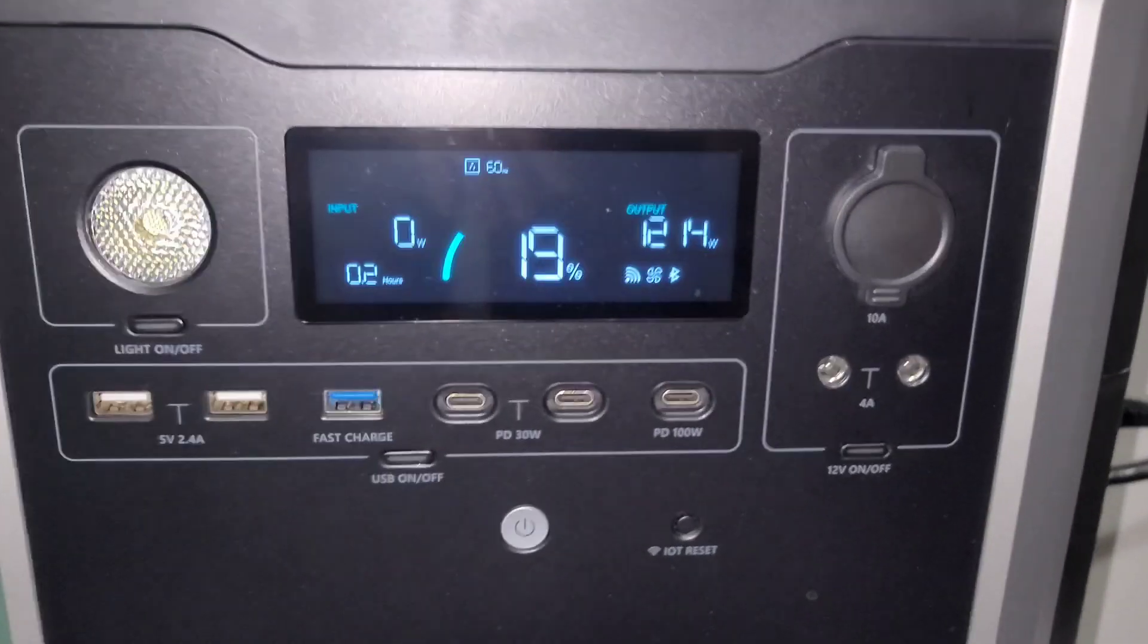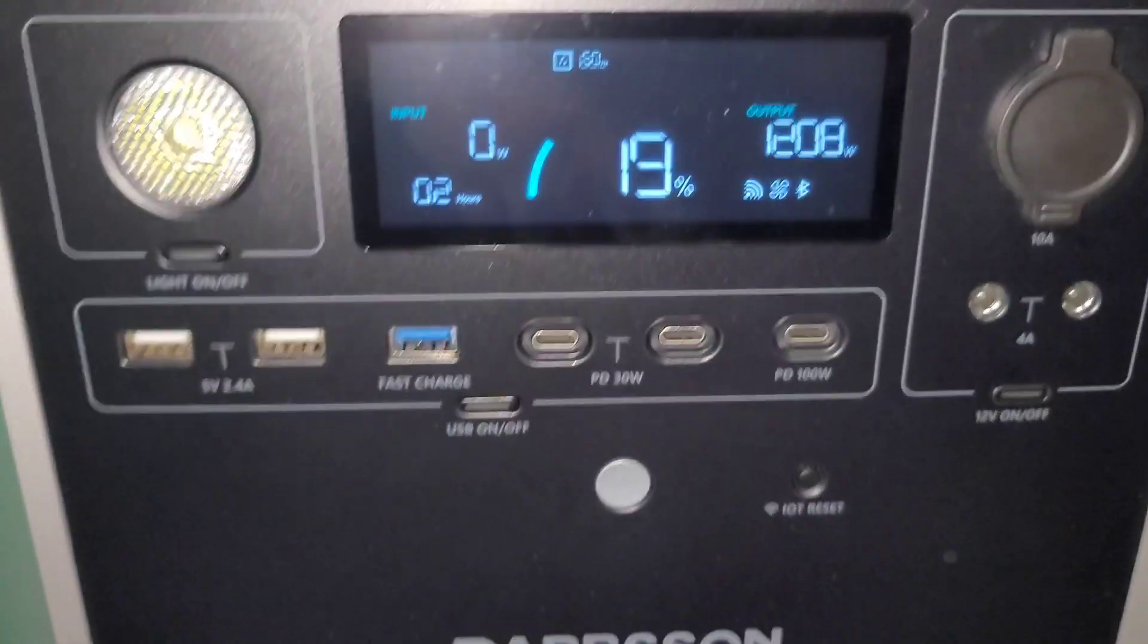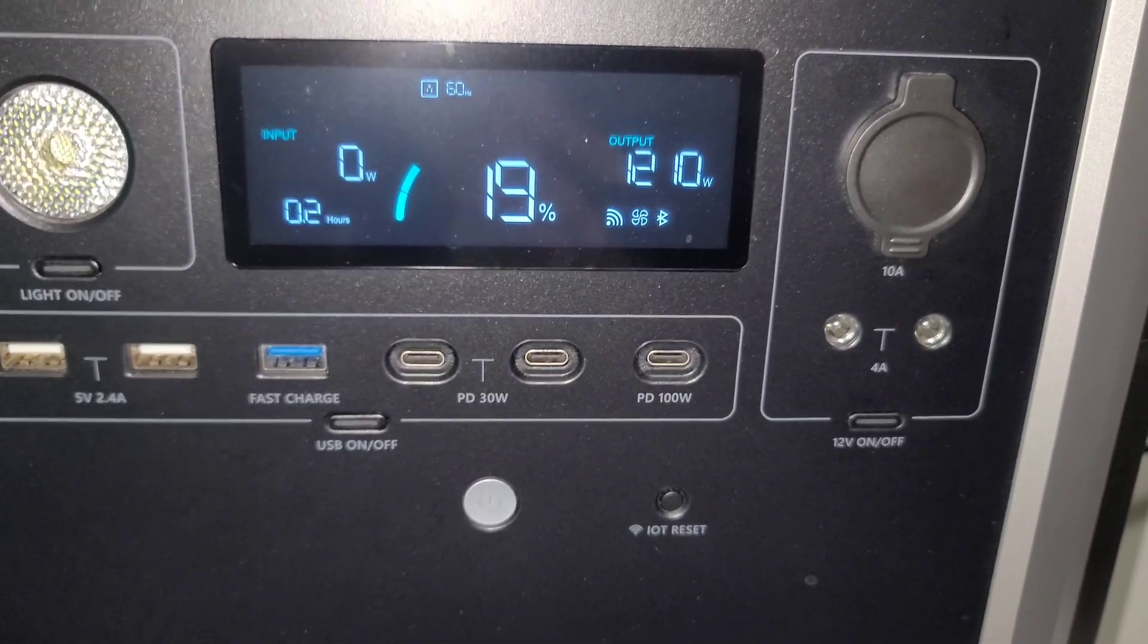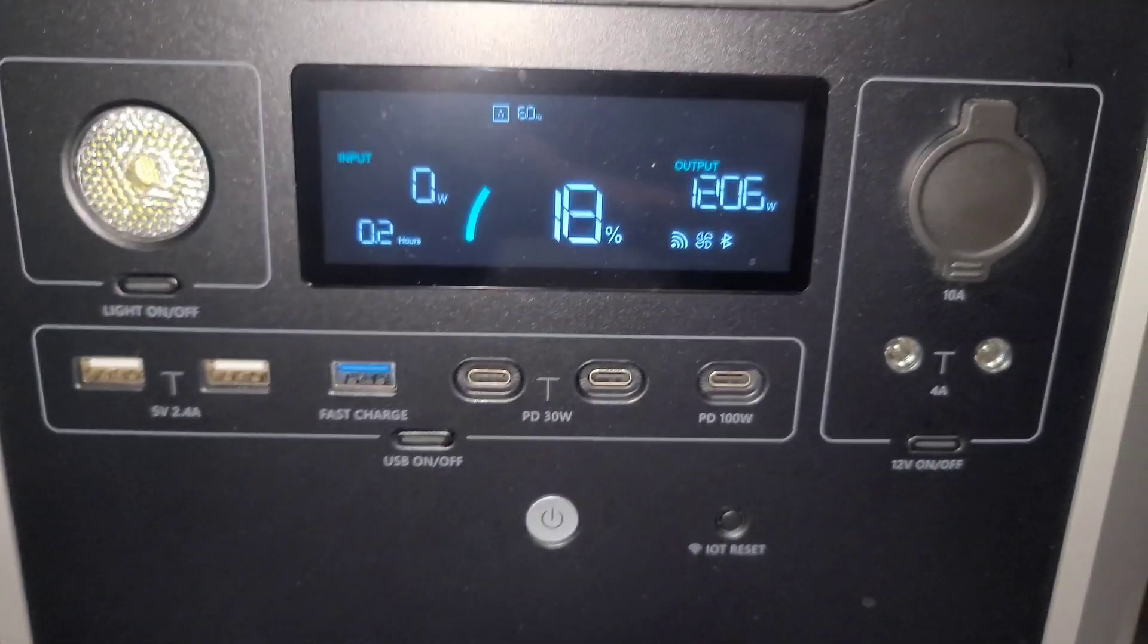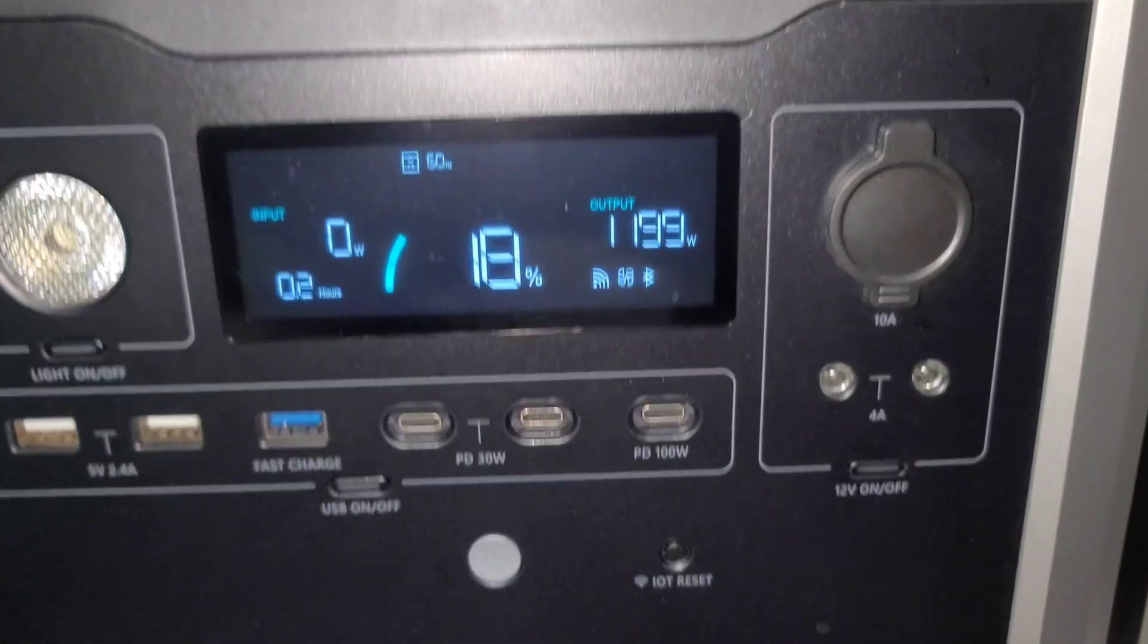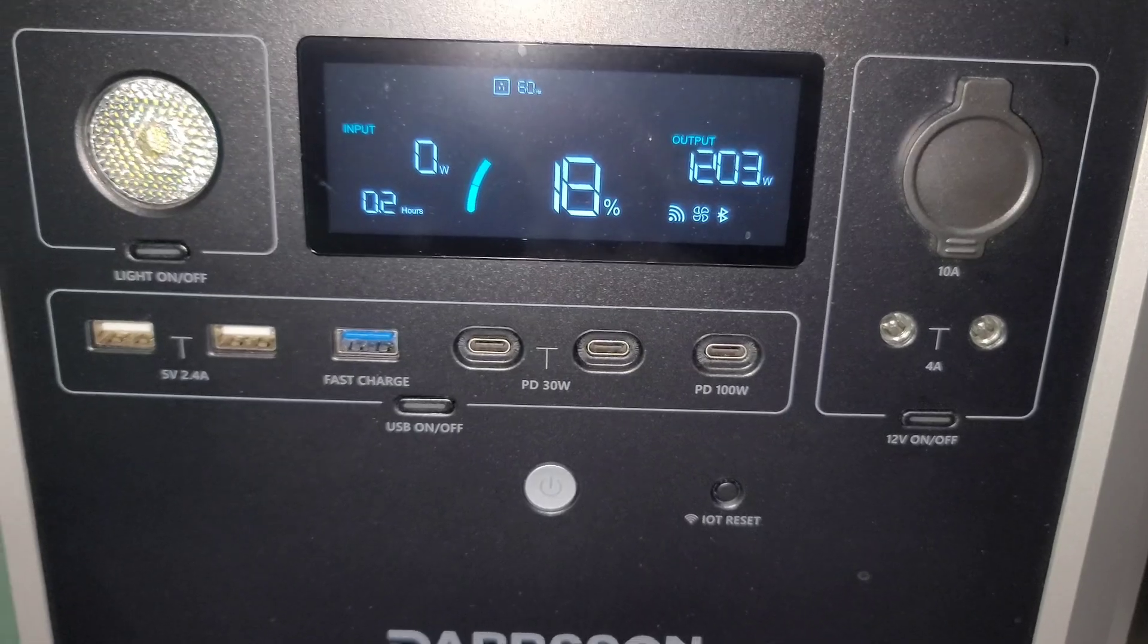This is a perfect example. This has been 1200 plus watts for, let's look at the kilowatt meter now. We're at 897 watt-hours and it's been running this for almost 44 minutes. That's a very efficient system. The unit's saying that we will get about 20 more minutes runtime out of this exact wattage. I haven't got the full reading yet but I will update that at the end of the video. I'm pretty confident that this thing is going to be like 90, 90 plus percent efficient. I've been doing the test on it and I've been getting around 84%, that's at a lower wattage though. I'm not going to be surprised if this thing actually pushes over 90% efficiency.